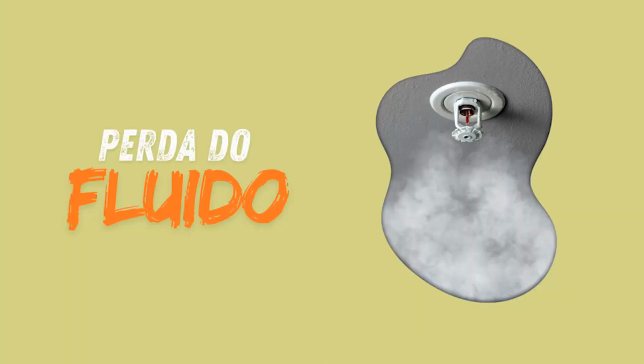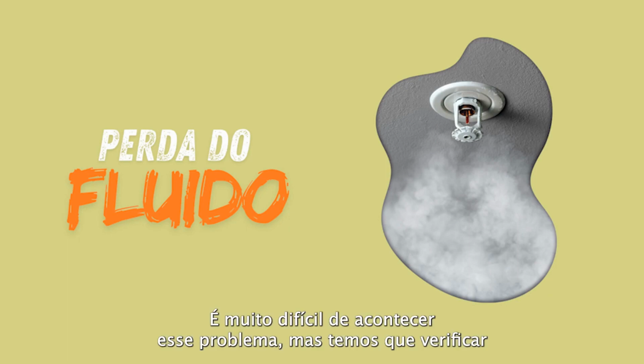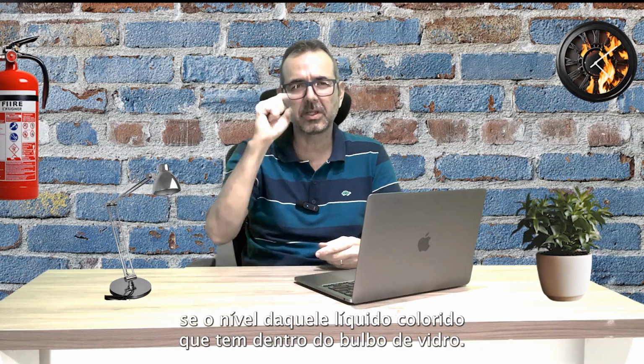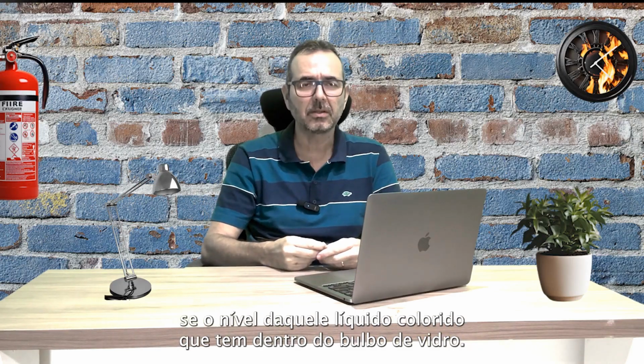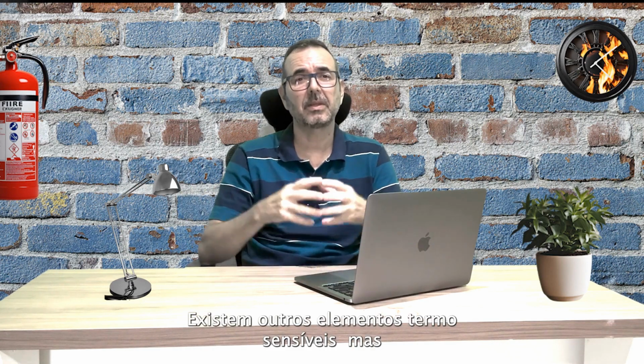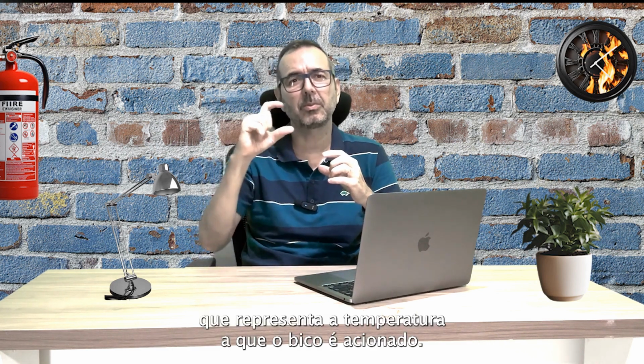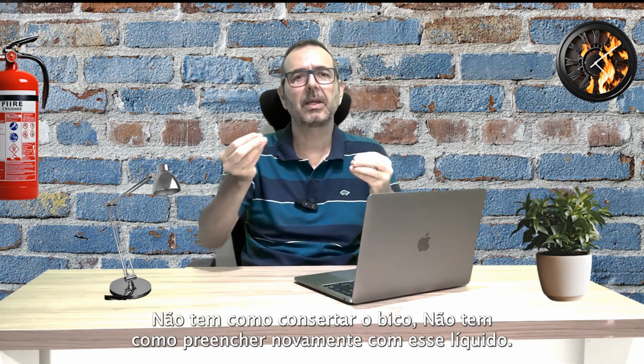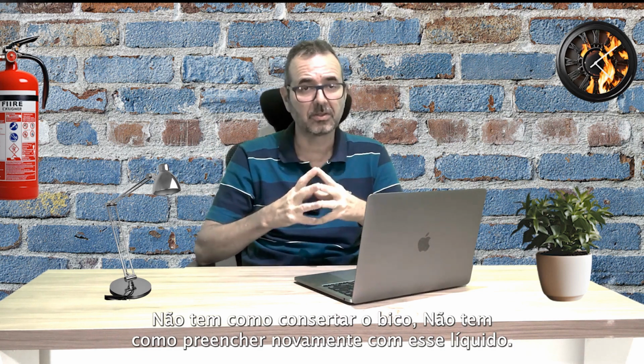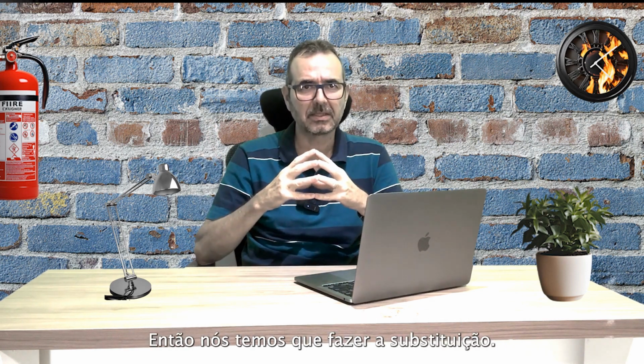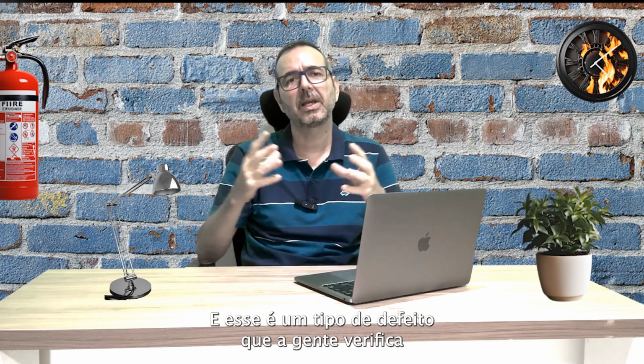Loss of fluid from the heat-sensitive element. This problem is very difficult to occur, but we need to check if the level of that colored liquid inside the glass bulb is adequate. There are other heat-sensitive elements, but the glass bulbs have a coloration that represents the temperature at which the nozzle is activated. If there is a leak of this fluid, we need to replace the nozzle. There is no way to repair the nozzle. It cannot be refilled with that liquid. So we have to make the replacement, and this is a type of defect that we check at floor level.